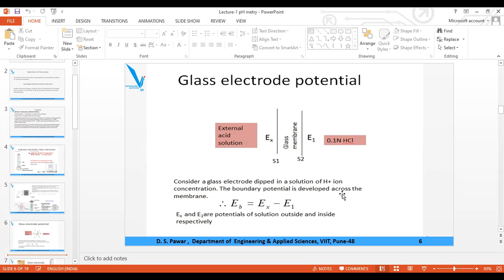So now this you have already done. This is what the glass electrode looks like. The price of this glass electrode is minimum 2 to 3,000 depending on the manufacturing company. Standard ones go 3,000 up, and this particular part is called the tip of the glass electrode, which is very fragile and sensitive. Even if you stir with pressure, this will break, the whole solution will come out, and then you have to throw it out. That is the disadvantage of the glass electrode, that the tip is very fragile. It can be broken easily even with a little high pressure applied for stirring the solution.